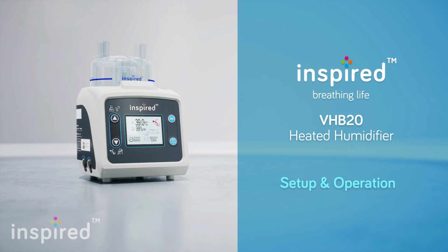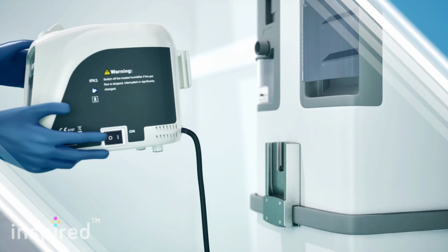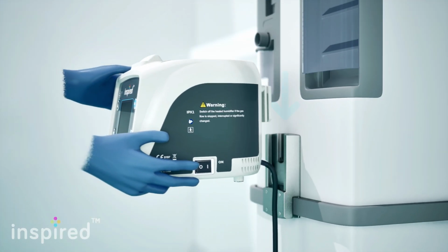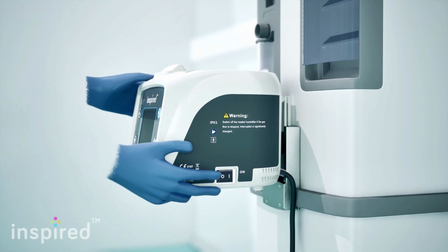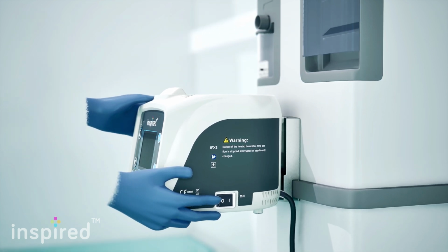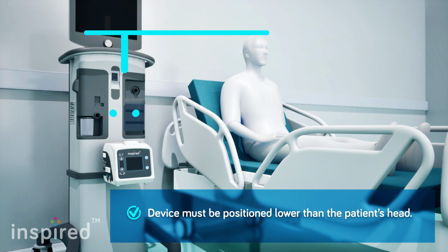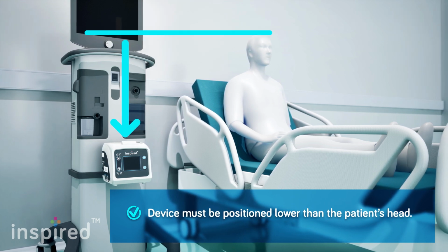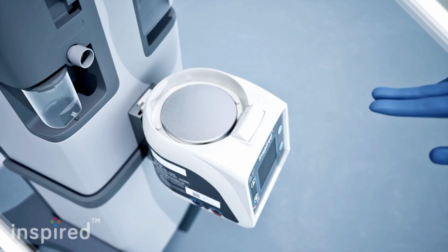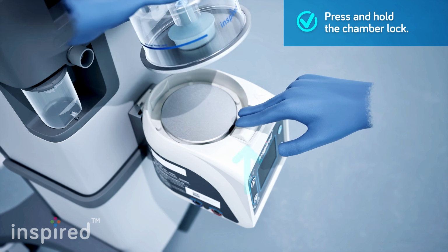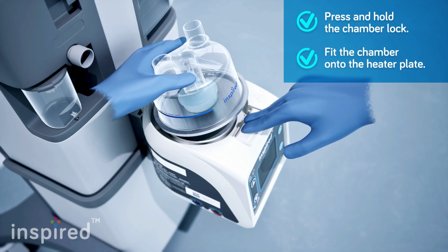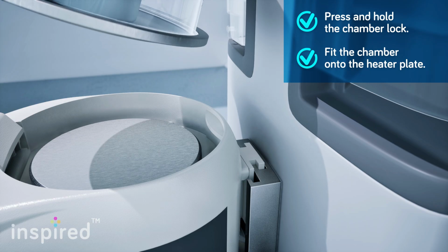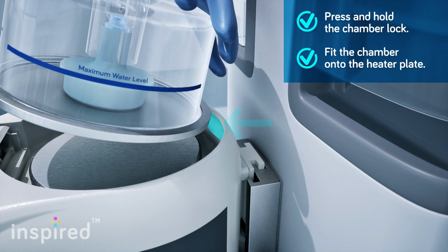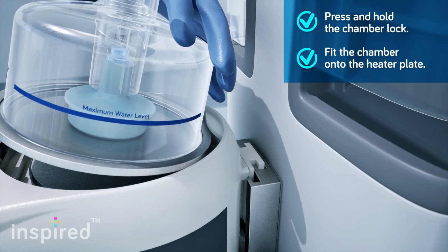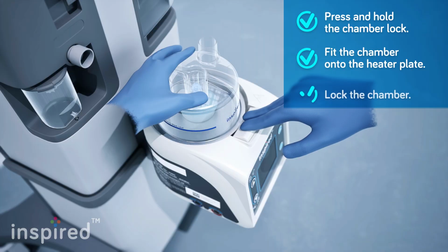Setup and operation. Secure your device by sliding the bracket located at the back downwards onto the clamp of the trolley. The device must be positioned lower than the patient's head. Press and hold the chamber lock. Fit the chamber onto the heater plate. Ensure the bottom of the chamber is secured beneath the guard board on the back, and lock the chamber.